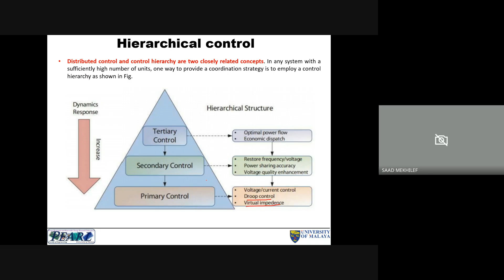If you look into the actual system, this is how it looks. We have the primary control here: the PQ droop control, reference generators, and then the inner control loops, the measured voltage and measured current, the modulators, and then we control the switches, and then the microgrid source. The secondary level is in charge of the voltage restoration loop and frequency restoration.